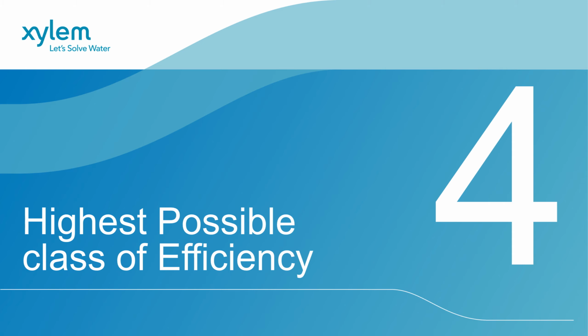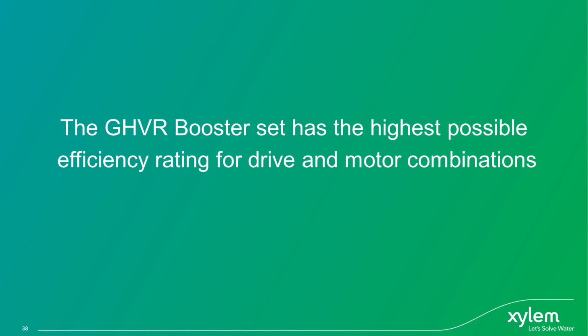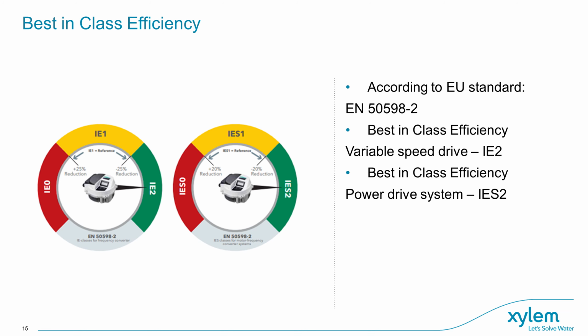The last key feature we will be covering today is the set efficiency. And to summarise, the GHVR booster set has the highest possible efficiency rating for a drive and motor combination. In 2014, the European Union put in place a new standard that for the first time defines the efficiency classes for inverters and electric drive systems. In this standard, it introduces the IE rating for inverter efficiency and the IES rating for the power drive system efficiency. Up until this point, there wasn't a standard that would rate the efficiency of how a variable speed drive operates, meaning installers would not be able to determine which drive in the marketplace was the most efficient.